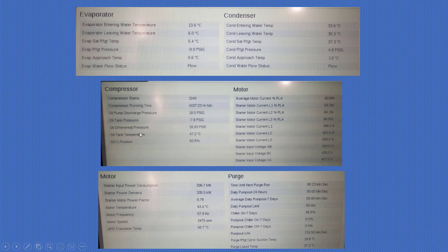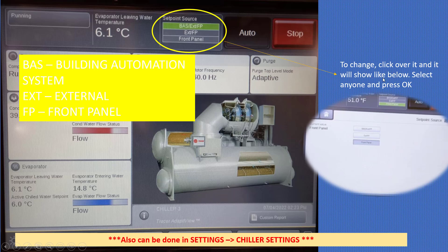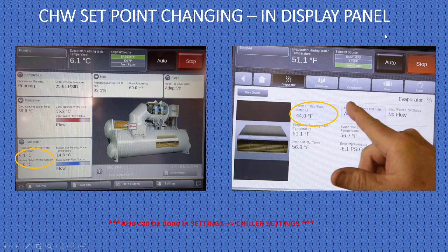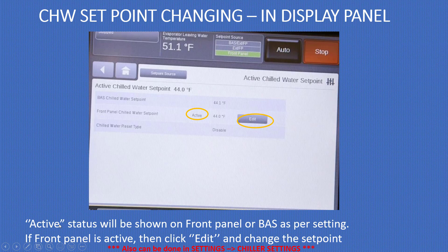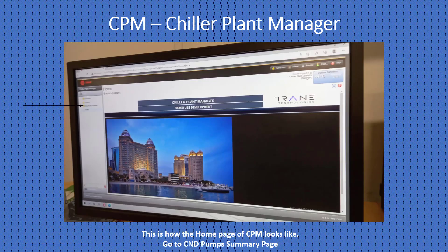The display panel is different from the CPM. CPM is monitored through a computer at the plant. For setpoint source to change, click on it and it will show the following — select any one and press OK. 'BAS' means Building Automation System, 'EXT' means external, 'FP' means front panel. This can also be done in the chiller settings. To change the chilled water set point in the display panel, go to the evaporator section and change the chilled water temperature. If the front panel is active, click edit and change the set points.